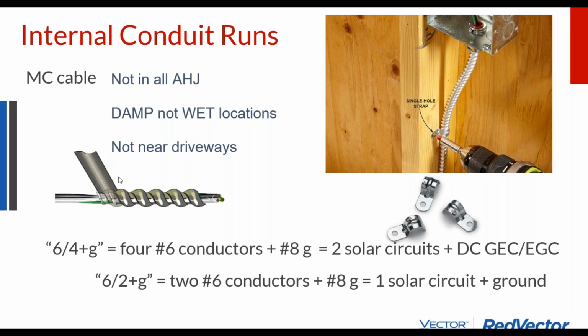And so on my residential solar arrays, I'm just running MC cable. Generally it's number 6 with a number 8 ground up to the rooftop. And if I'm using 2 circuits of solar, I have two positives, two negatives, and a ground. If I have one circuit, or if I'm jumping between different sections on the roof from one subarray to another subarray with one circuit going in between subarrays, I use number 6, 2 MC cable and a ground. And this just gets strapped to your rafters, and it installs very easy.